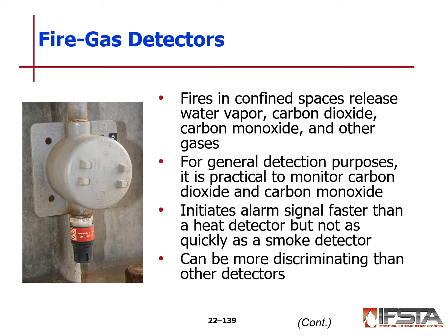Fire gas detectors. Fires in confined spaces release water vapor, carbon dioxide, carbon monoxide, and other gases. For general detection purposes, it's practical to monitor carbon dioxide and carbon monoxide. This initiates the alarm signal faster than a heat detector, but not as quickly as a smoke detector. They can be more discriminating than other detectors. These are usually specific to a specific gas.